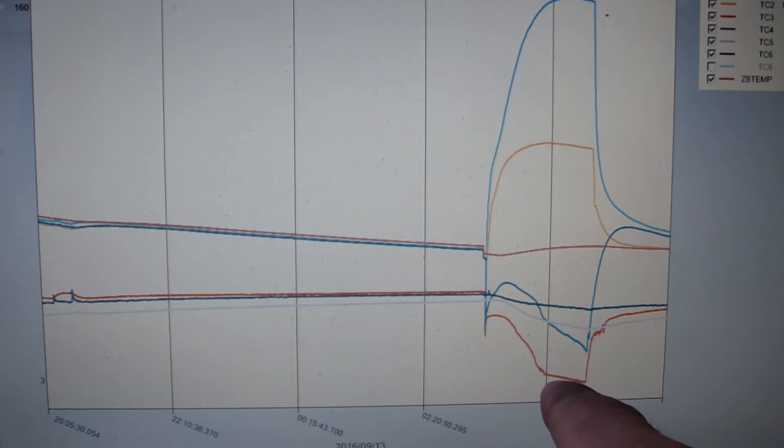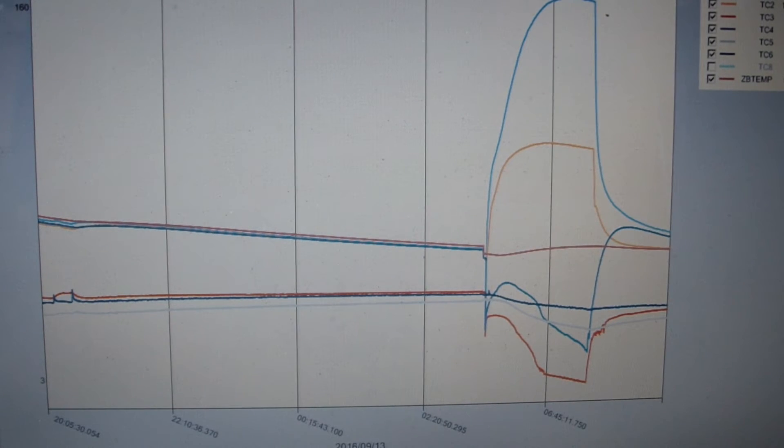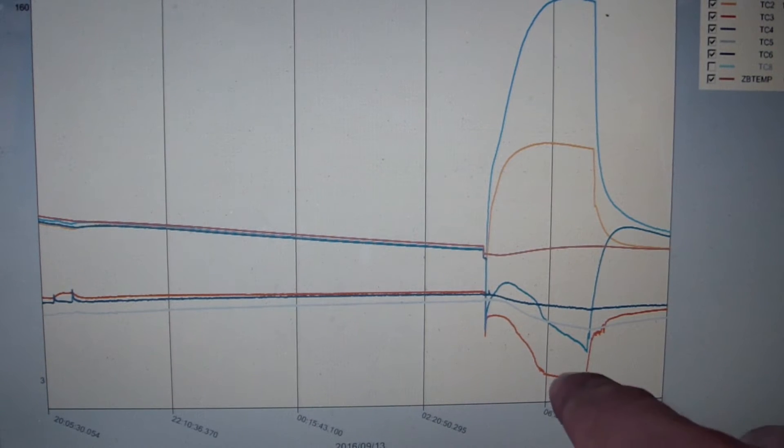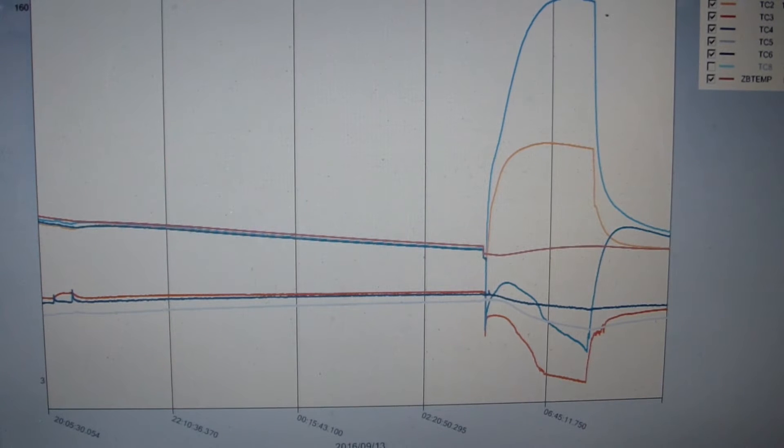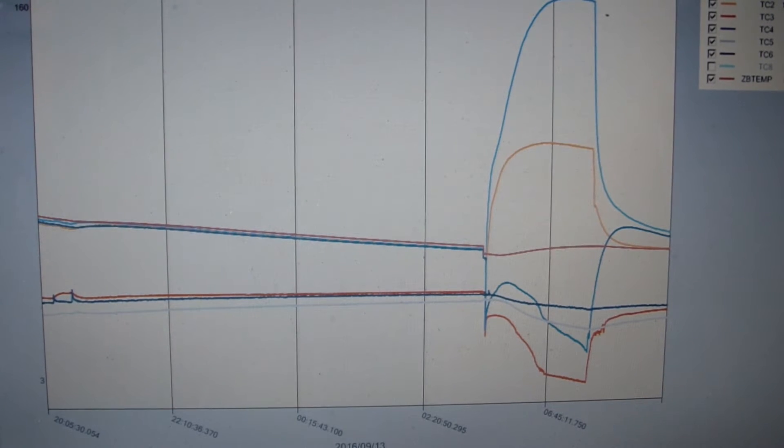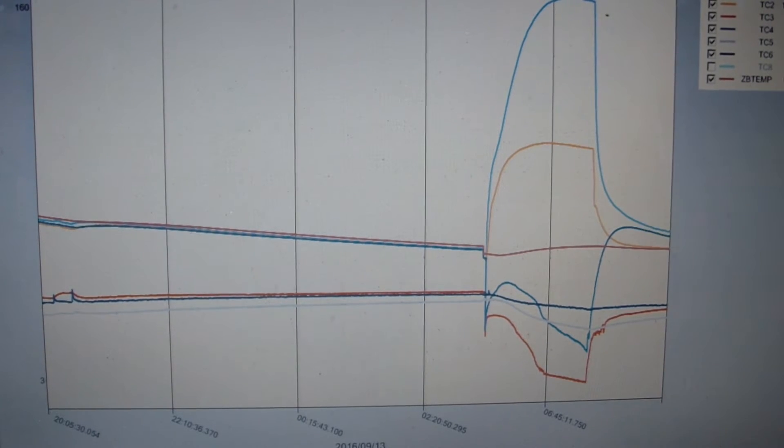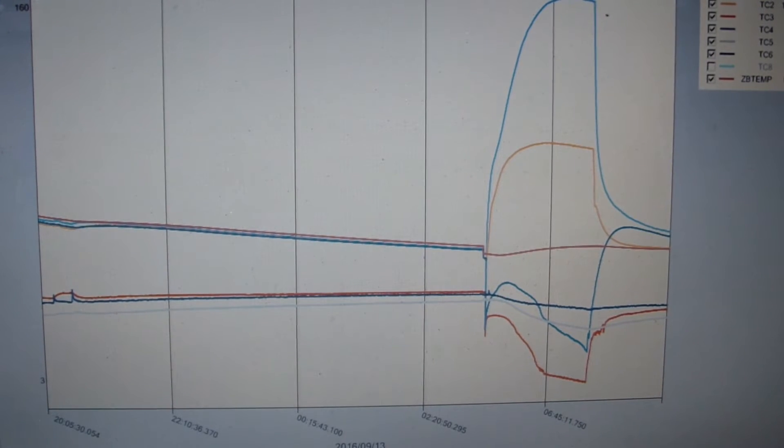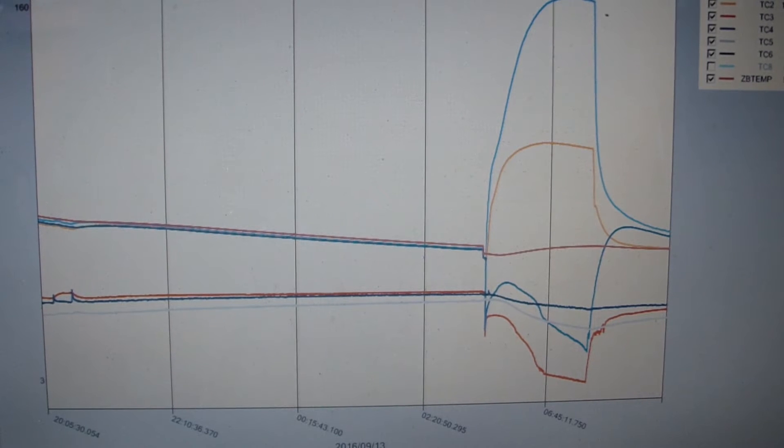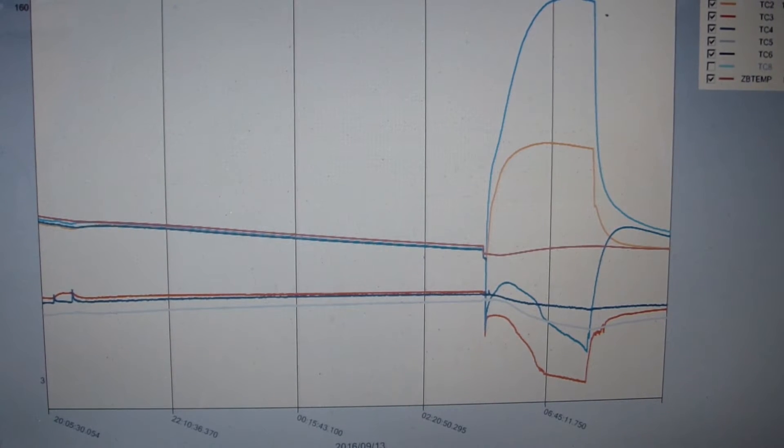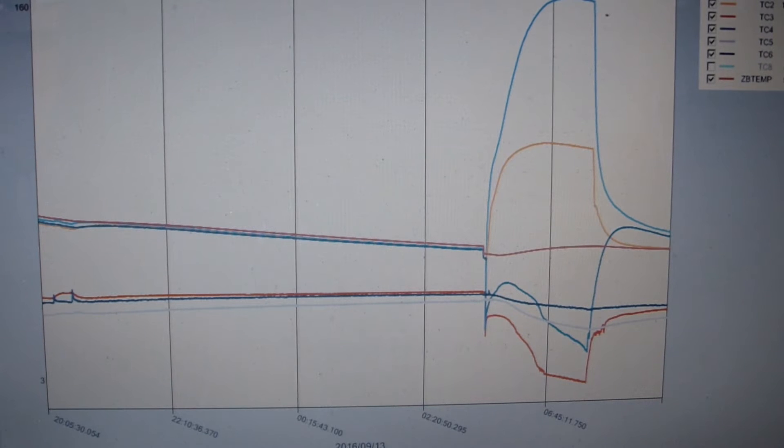Once it flattens out and the temperature of the box continues to lower and the low side pressure falls, the superheat value goes with it as it stays well saturated. Like I said, I added a little bit of refrigerant to try to push a little more into the low side. I probably have a small leak.